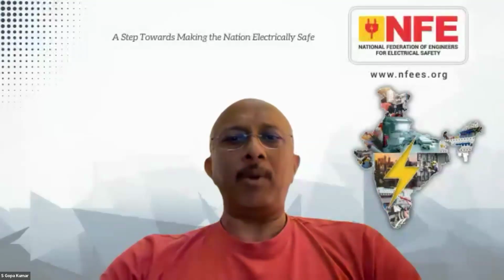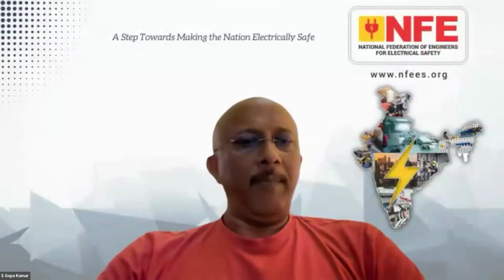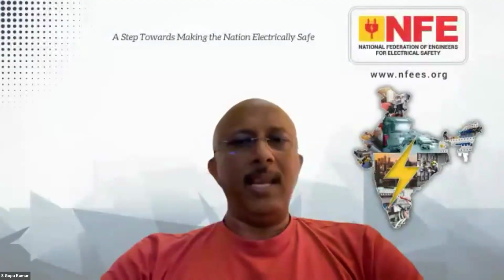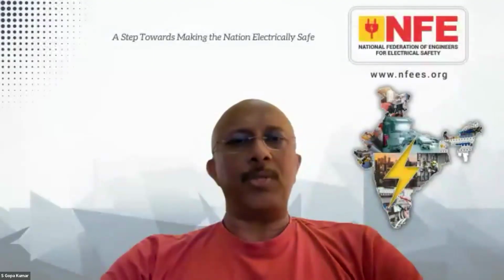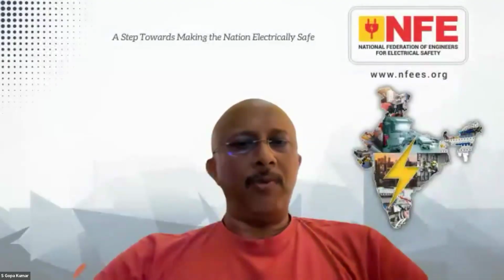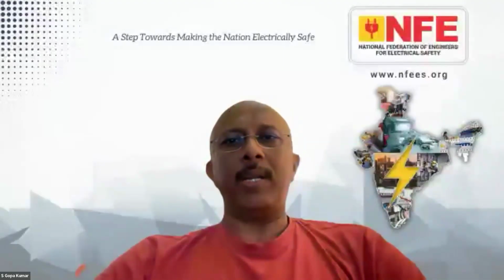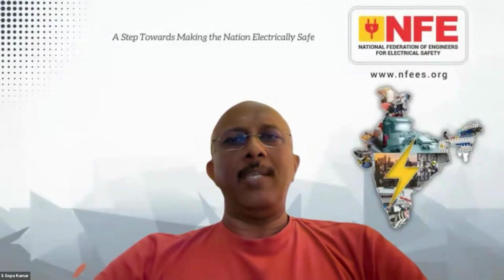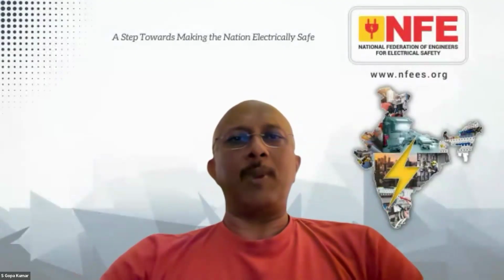But over a period of time, the RDSO was the first one, in 2003, to specify that only encapsulated spark gaps are allowed in railways, and over a period of time a lot of developments happened. Now today, one of the challenges the market faces is the length of the wires used in SPDs. Majority of the customers, the users, don't care about the length of the protective conductors, the wires used to connect the SPD. As a result, the effectiveness of the SPD is quite less. Anyway, the speakers will explain more about this.